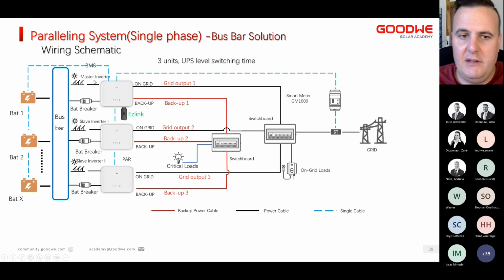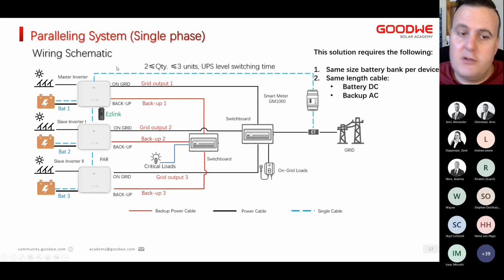especially if you only have PV on, let's say, 1 or 2 inverters and not on the 3rd one, because you have a higher peak demand and not so much load demand in total. But the inverters, even in this configuration, should compensate for that. So if one inverter does produce more PV than the other inverter, and this one starts to essentially export that power, then one of the other inverters will consume that power to charge the batteries.